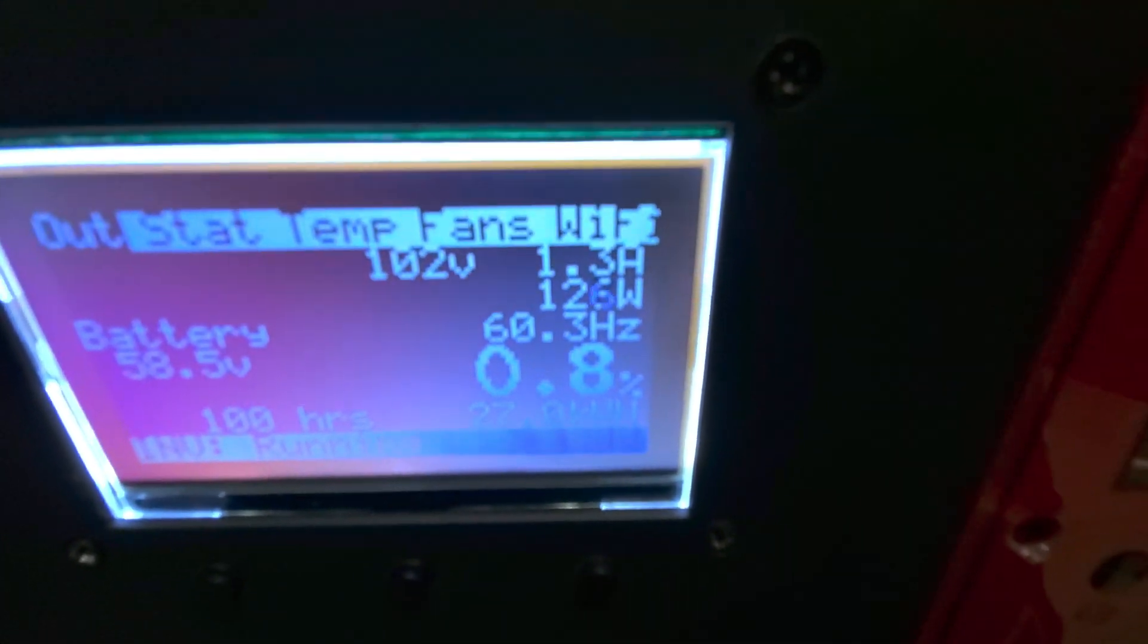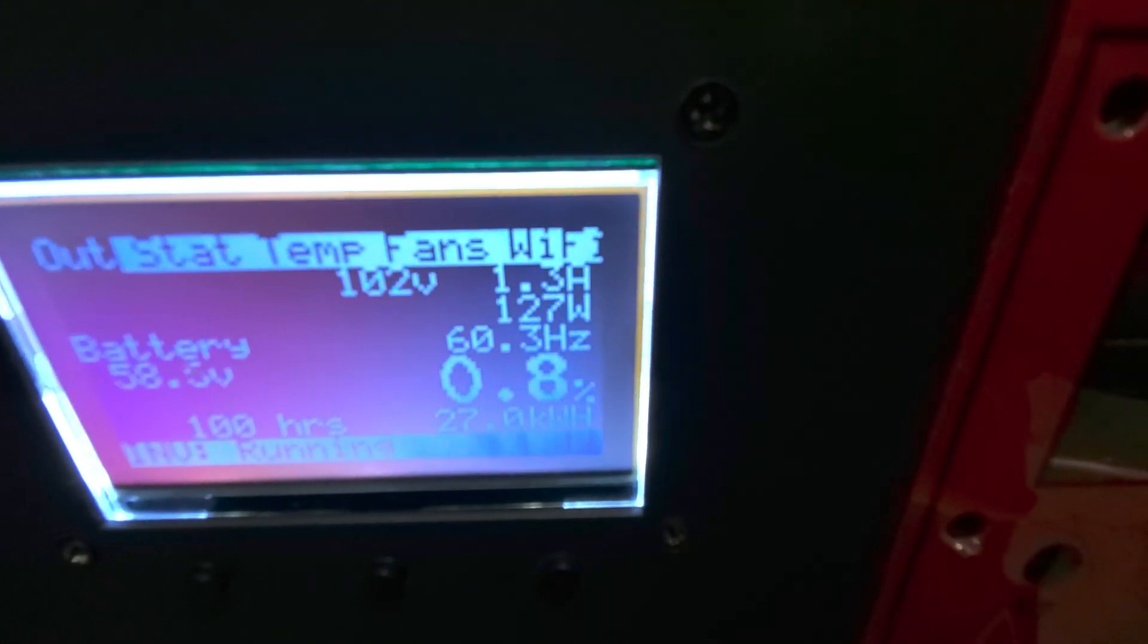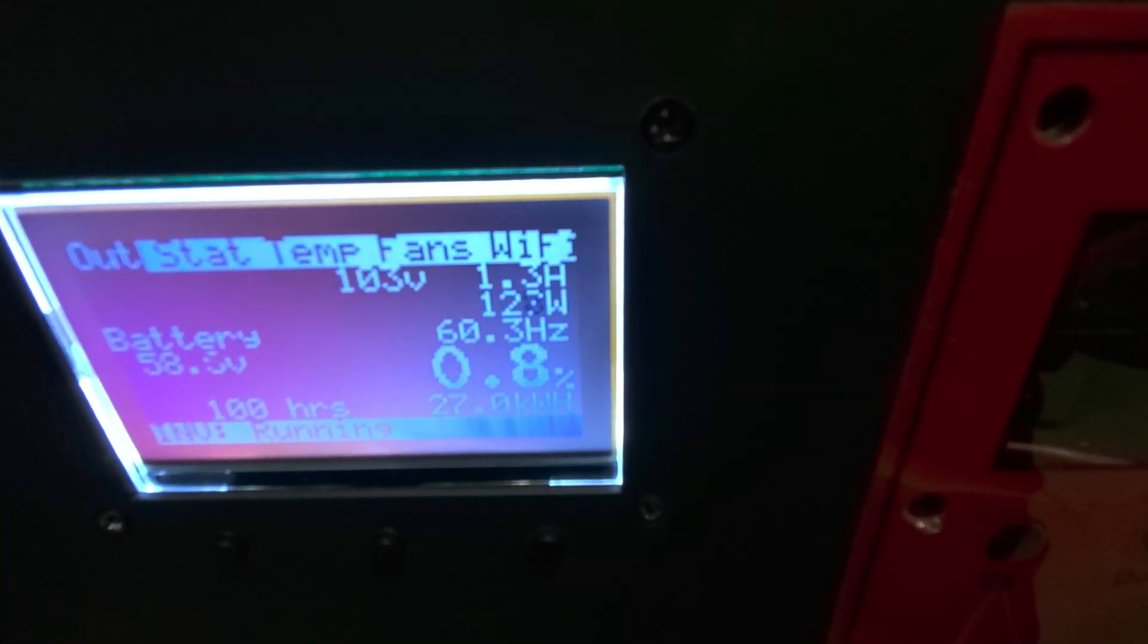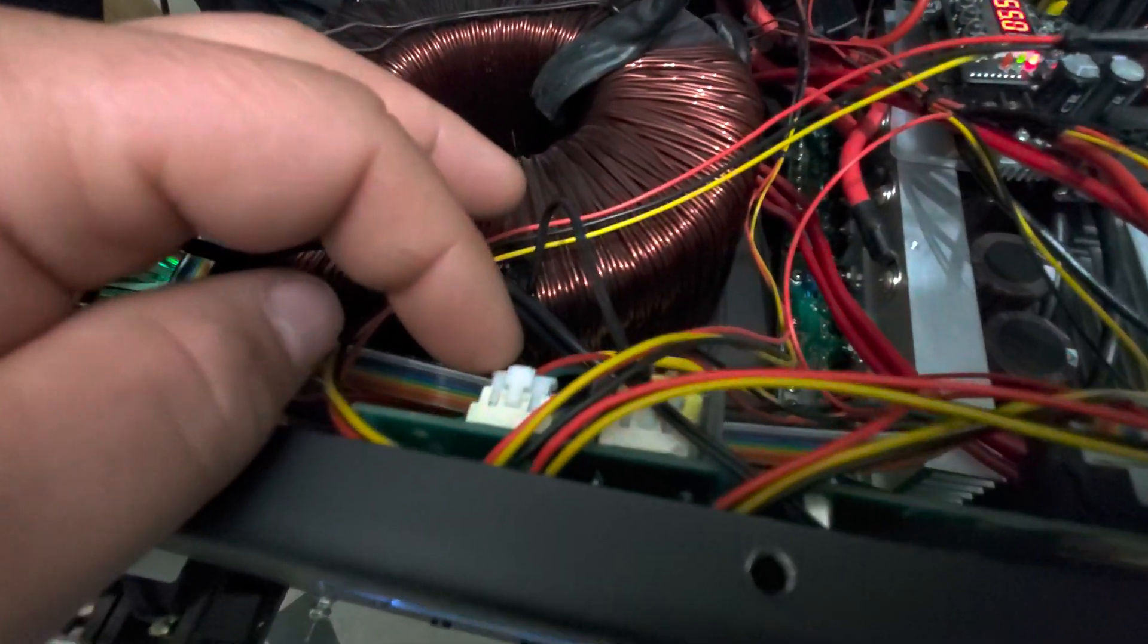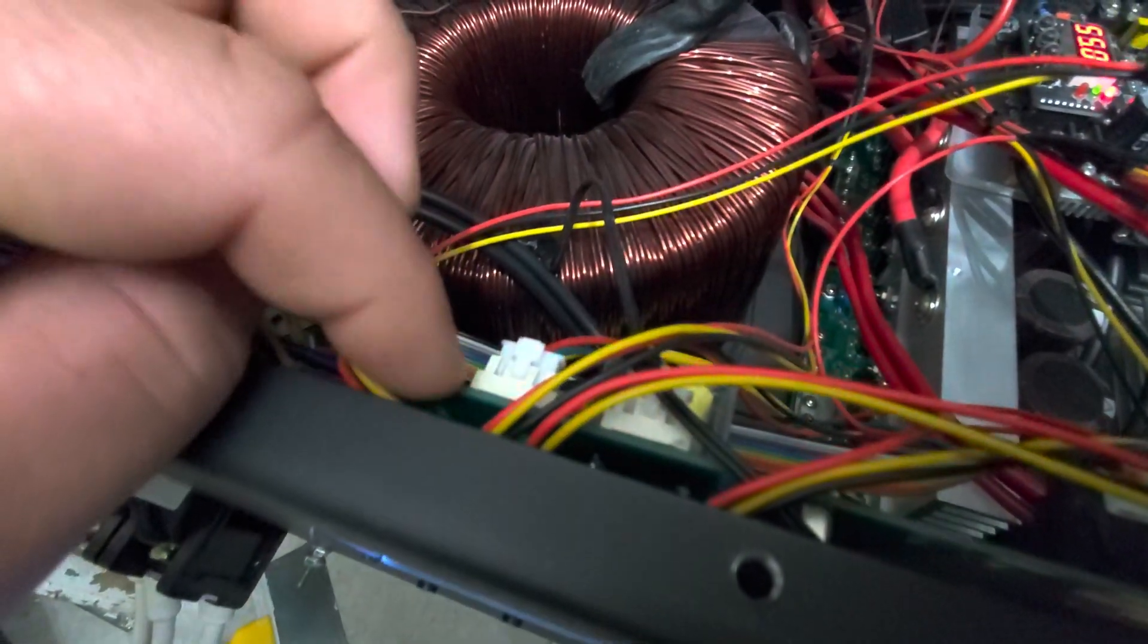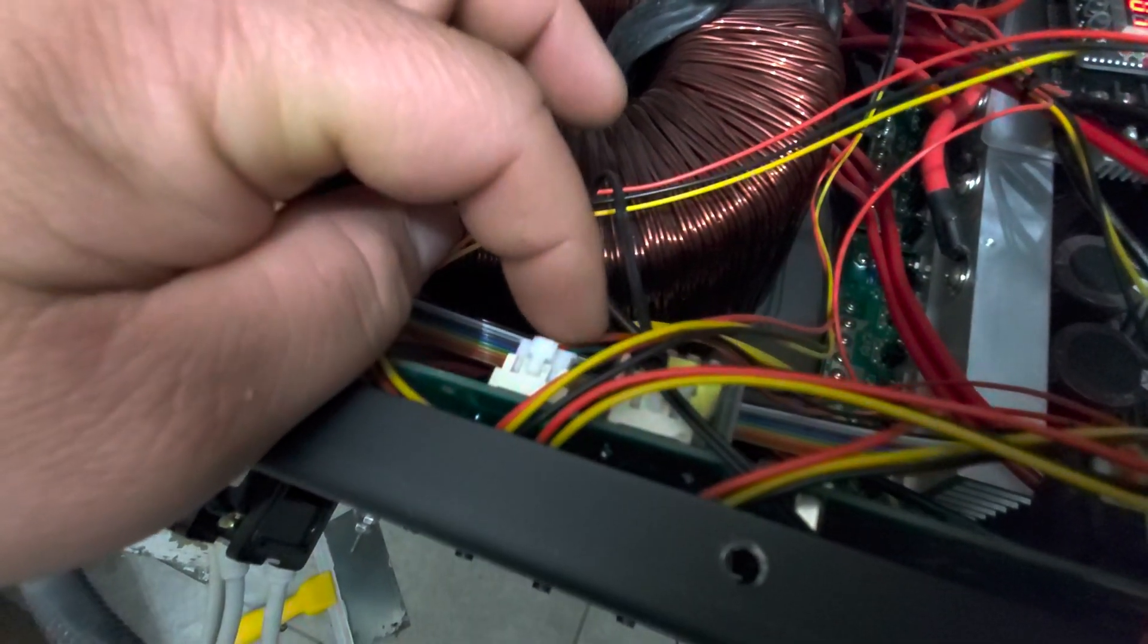And you can see here how it's moving around as I wiggle and shake it. Look at that, it's going all over the place. So unfortunately that affects the calculation on load. It actually affects the load because you can see my load has actually changed as it goes on, and unfortunately I can't really calibrate this without actually fixing this harness.